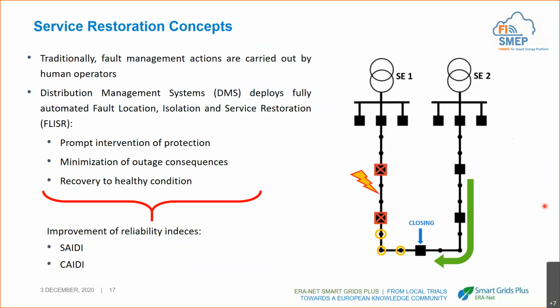And what we reach is a prompt intervention of the protection and minimization of the risks for the people, and also a minimization of the consequences to the devices that are experiencing overvoltage and overcurrent. And this increase of reliability for the grid is quantified by, in particular, I reported here 2 indexes. The first is SAIDI, which is an average of the duration of the faults, of the outages in 1 year, and the second one is the SAIFI, which is considering the number of customers that we have in the grid.